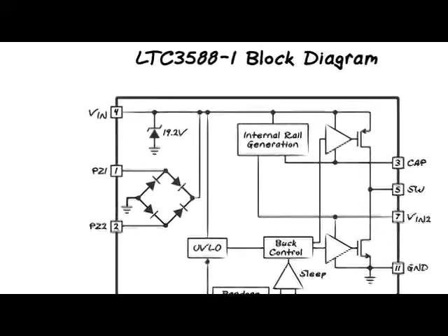The output of that would go into our input storage device. We also have a voltage clamp, which clamps the voltage on the input storage element to 19.2 volts, extracting any excess energy above that to protect the device. The shunt current for the clamp circuit can sink 25 milliamps from the input bridge rectifier.